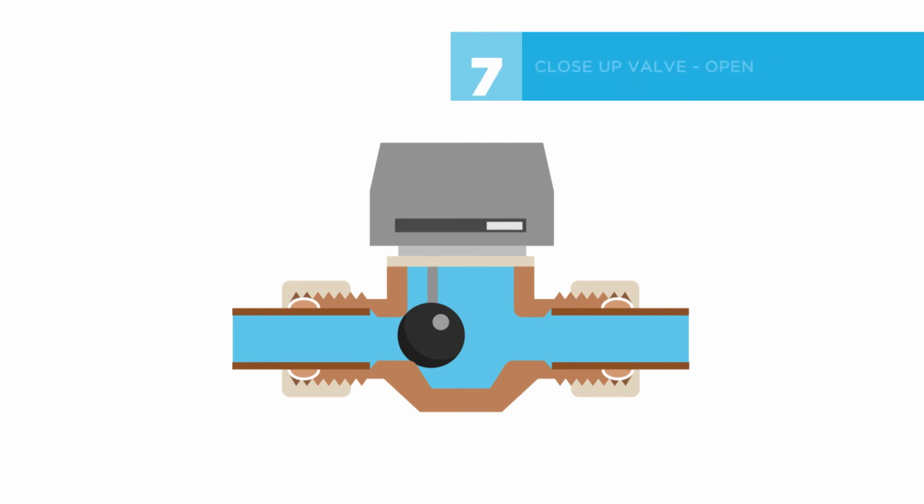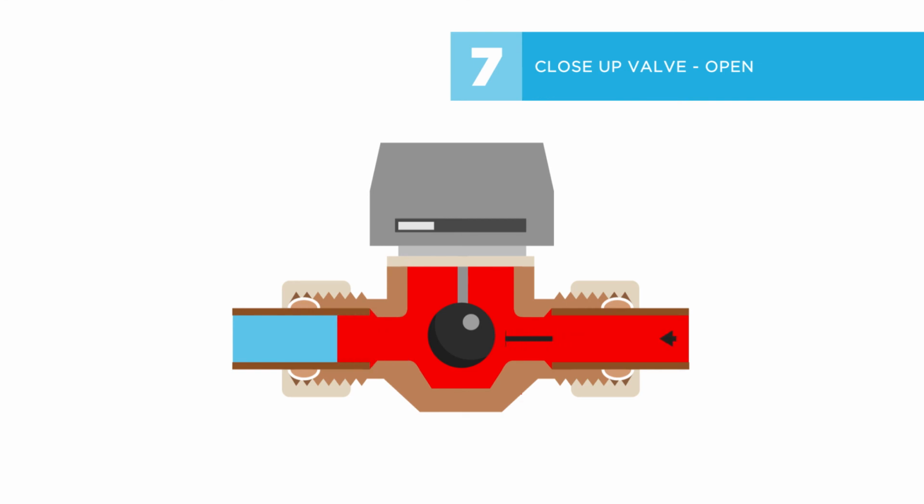There is now a signal from the thermostat to the zone valve, therefore the valve is now in the open position as the rubber paddle is moved from the port and heated water will flow to the circuit. The synchron motor has rotated, moving the rubber paddle, freeing the flow of water and making or connecting the micro switch which activates the pump and boiler. The synchron motor is located in the head of the 2-port valve.